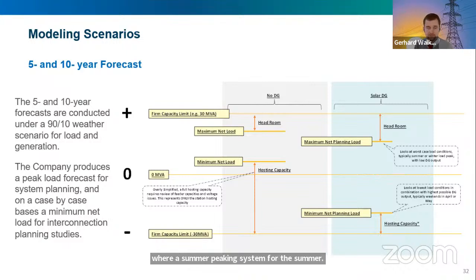On a case-by-case basis, where we're faced with interconnection requests that require a study, we create a minimum net load for the interconnection studies. That minimum net load includes all the queued DER prior to the currently interconnecting request. Since it's first-come, first-served, it does not include any forecasts past that point, because the DER has the right to be studied only under consideration of the system as is, up to their point in the queue. So that minimum net load scenario does not include any long-term forecasts - it's a status of the system at the point of interconnection. So those are the two scenarios.